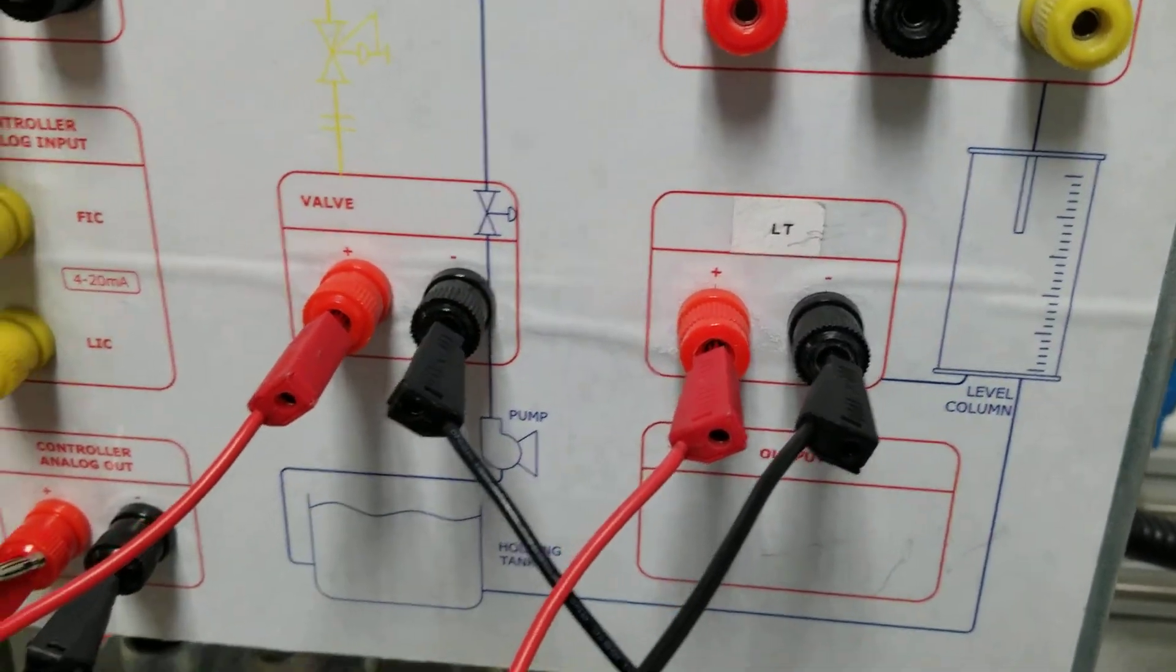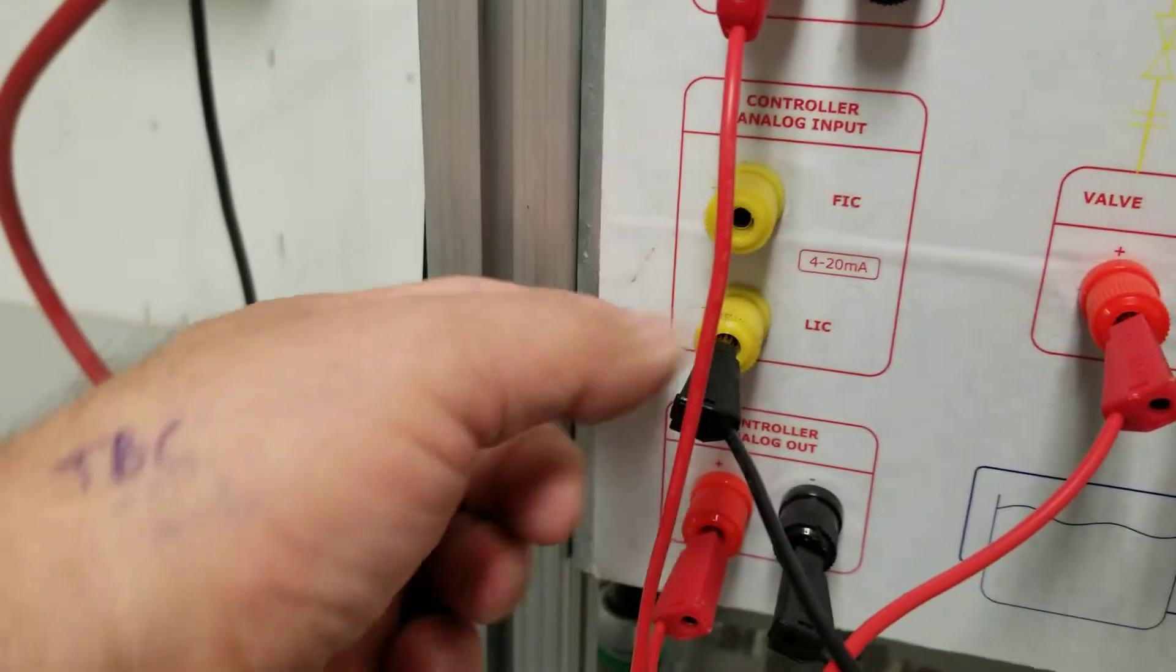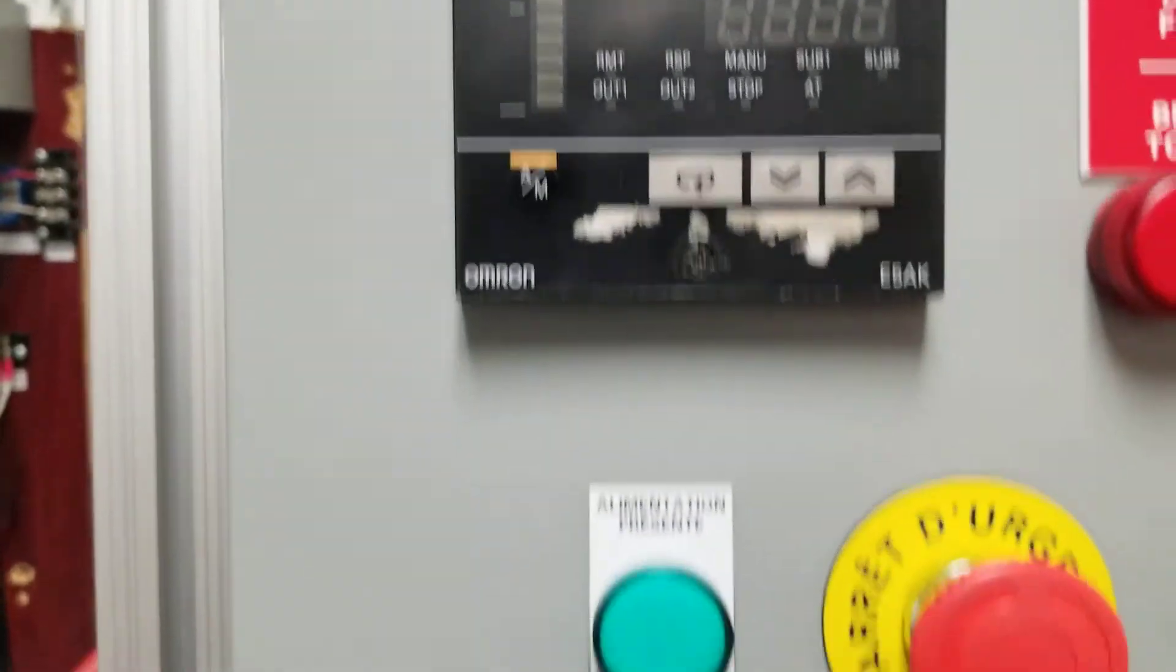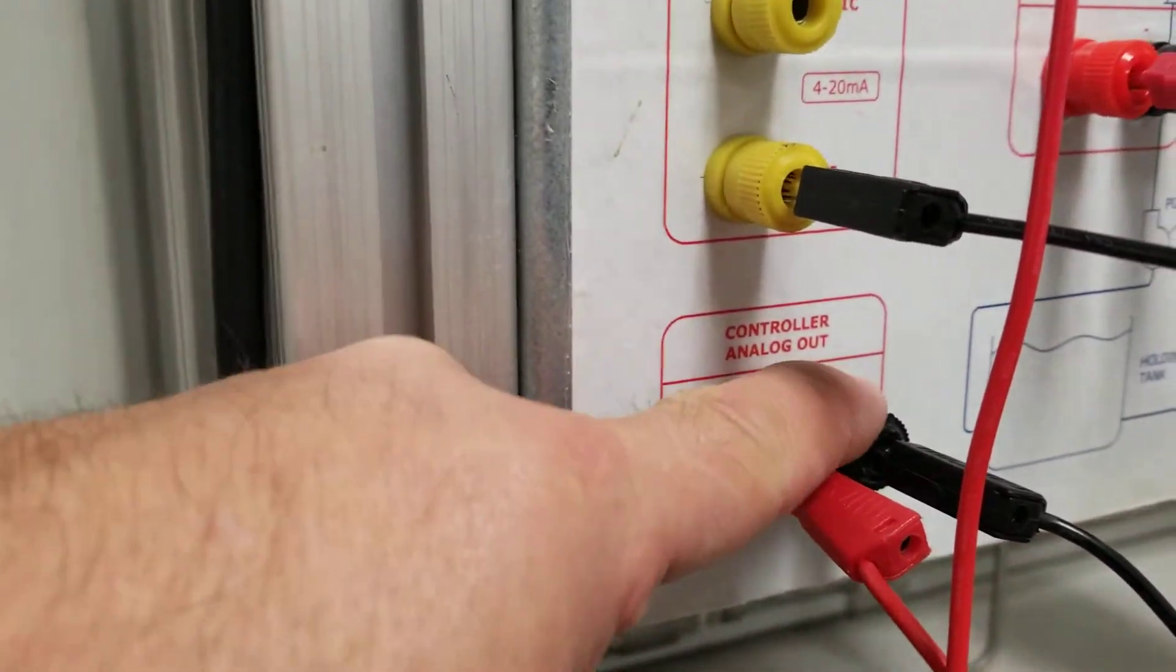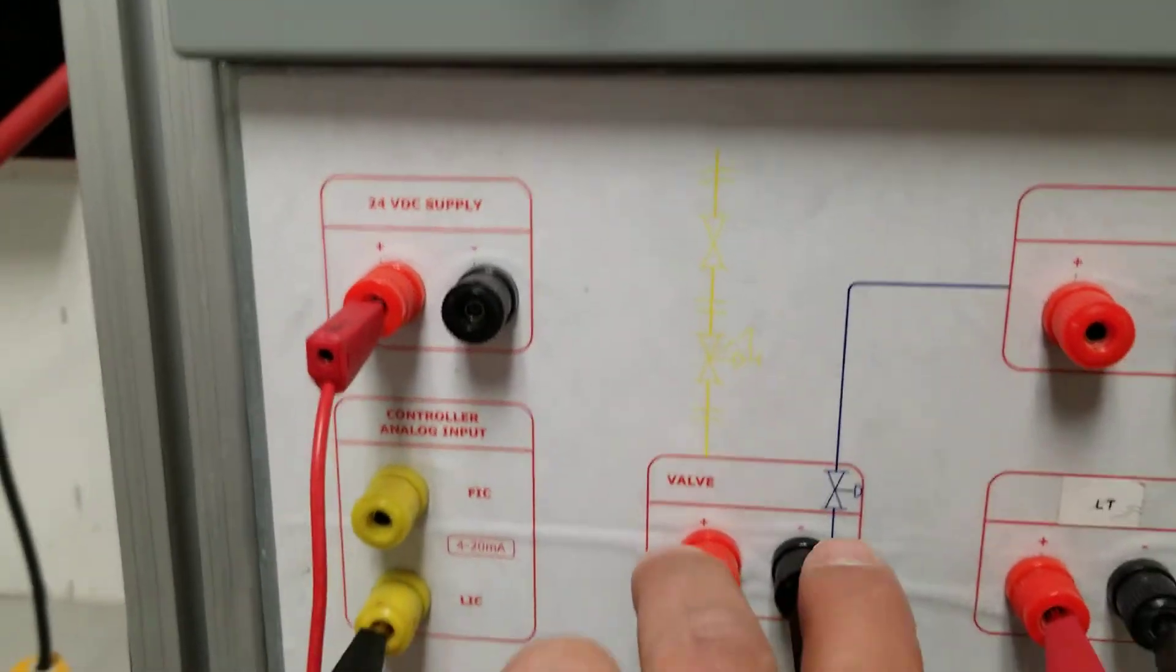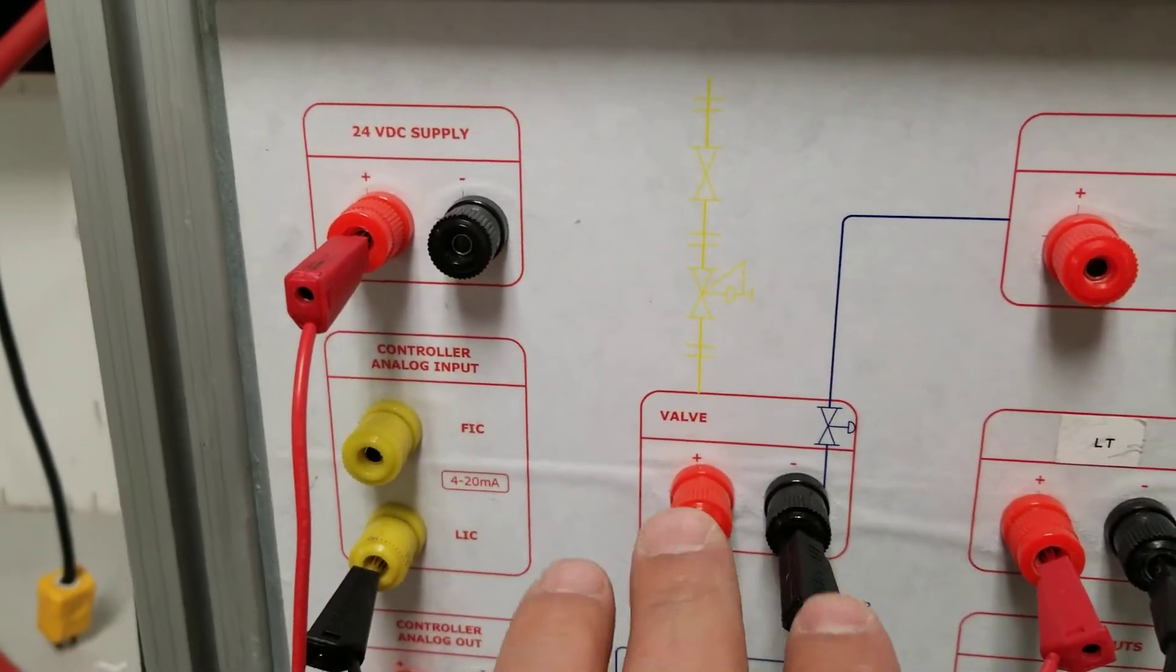So this guy here is the controller. The output of the controller, right here your positive and negative, will go straight to your I/P converter before going to the valve that will open up the positioner.